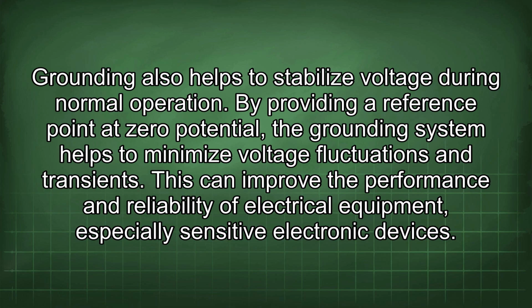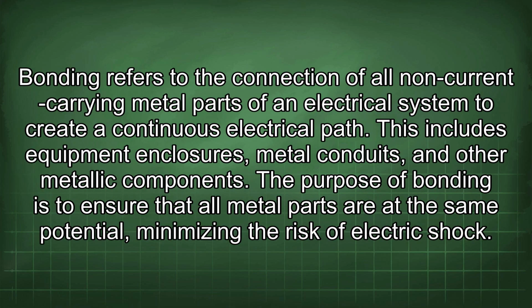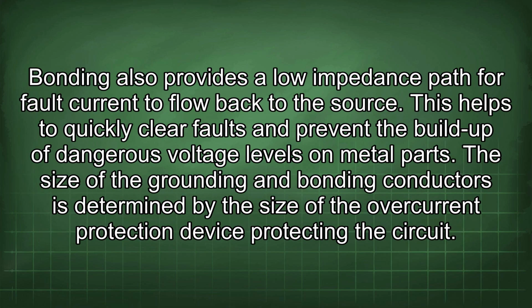This can improve the performance and reliability of electrical equipment, especially sensitive electronic devices. Bonding refers to the connection of all non-current carrying metal parts of an electrical system to create a continuous electrical path. This includes equipment enclosures, metal conduits, and other metallic components. The purpose of bonding is to ensure that all metal parts are at the same potential, minimizing the risk of electric shock. Bonding also provides a low impedance path for fault current to flow back to the source. This helps to quickly clear faults and prevent the build-up of dangerous voltage levels on metal parts.